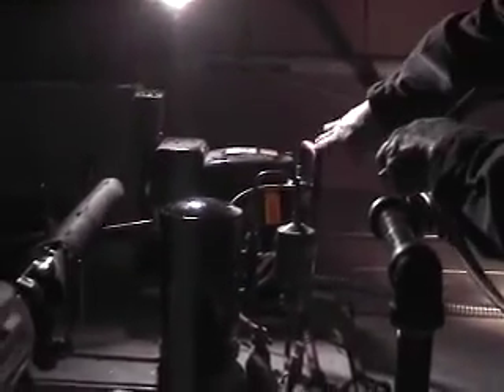That does have a low pressure cutout. Yes. The low pressure side here, and then the high pressure side set for about 325. What you don't want to do is stress your compressor by taking it too high, which is why we go to this point. Plus, it'll just go back and forth.